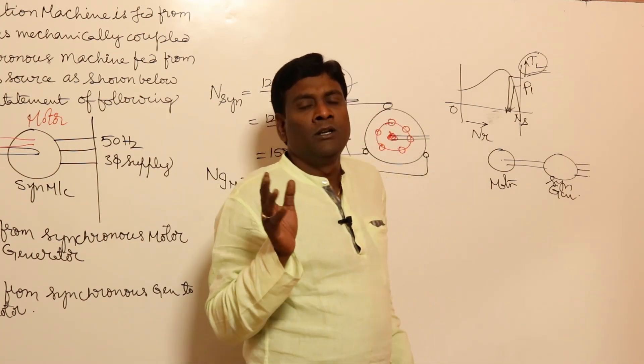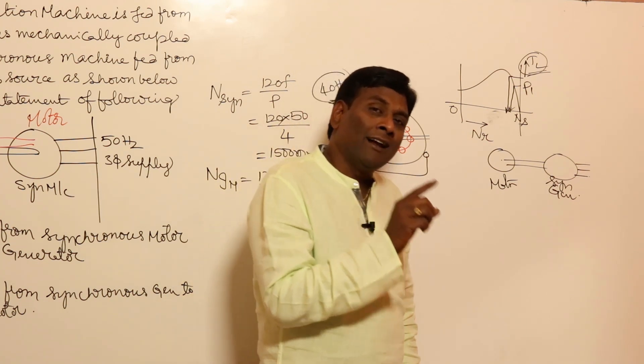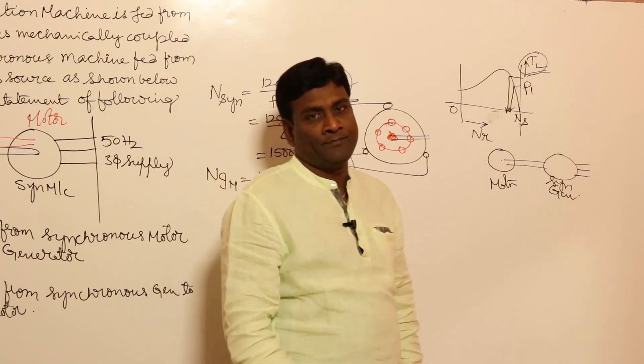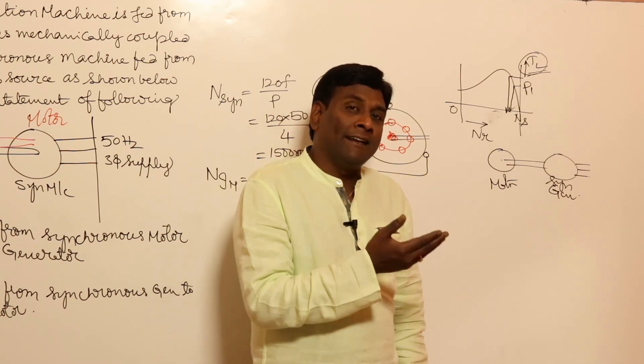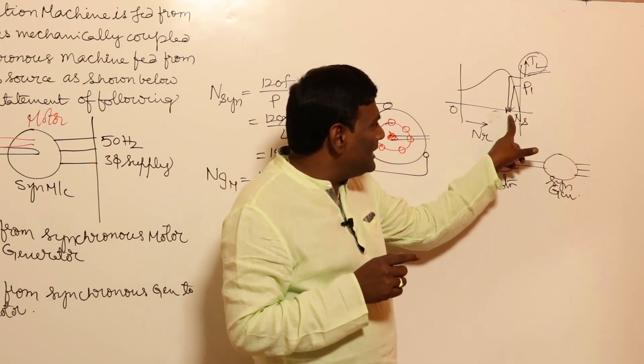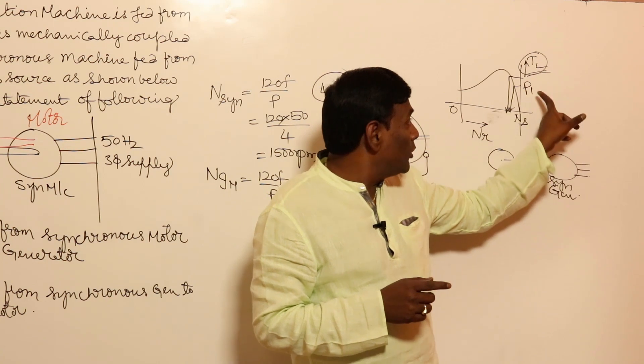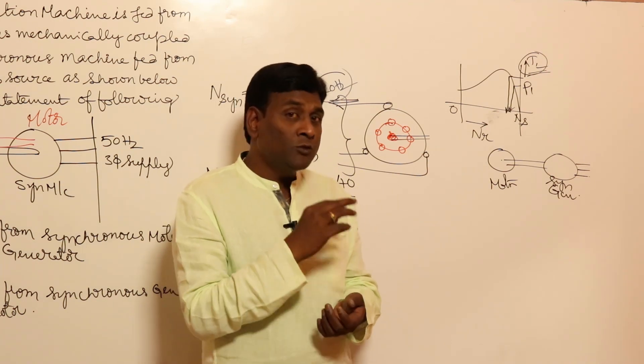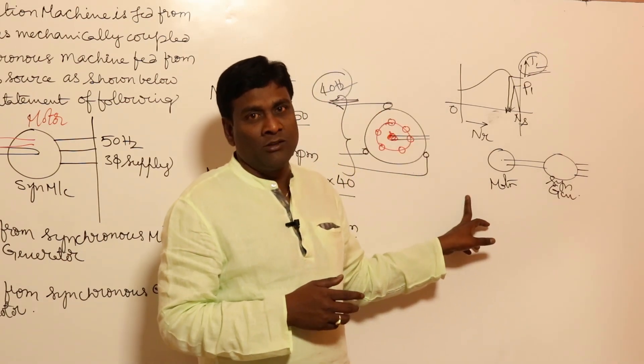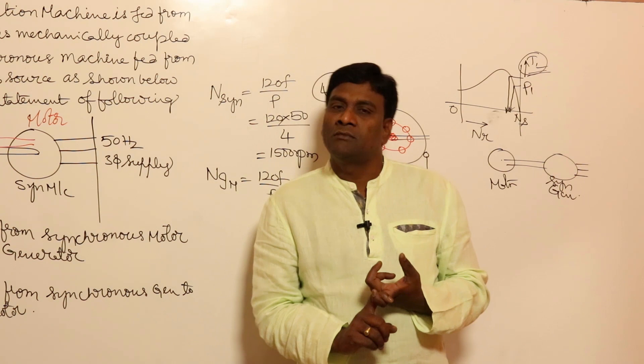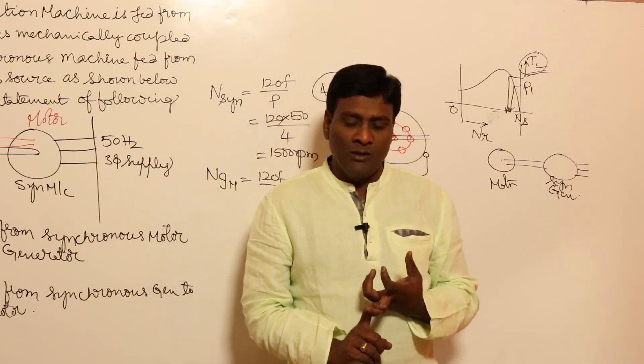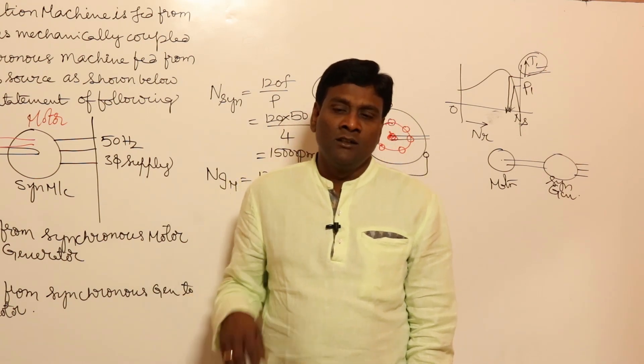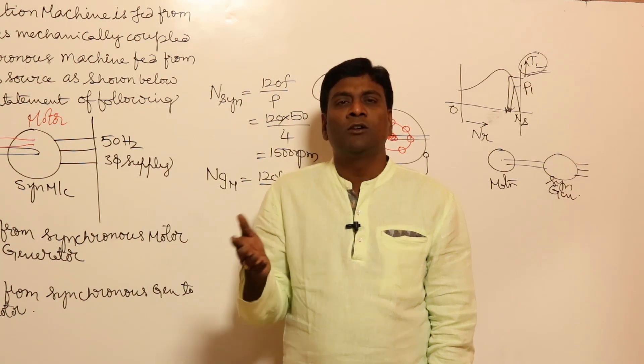In conclusion, an induction motor can be used as a prime mover for an isolated alternator — under isolated conditions, frequency variation is acceptable. But for a grid-connected alternator, the induction motor can only deliver one specific power level at one specific speed. Power variation is not possible in the basic setup. However, two variations are possible for grid connection: rotor resistance variation or variable input frequency control — these will be discussed in the induction generator isolated condition problem and speed control of induction motor topics.